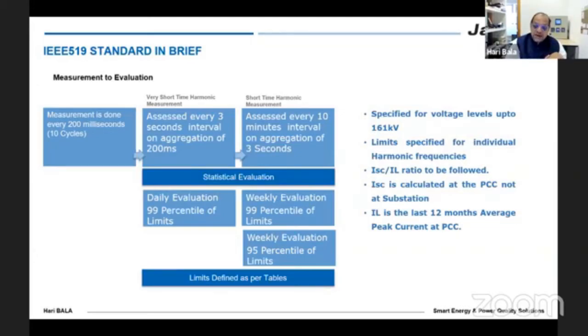Then they say the ISC by IL ratio depends on the location of the point of common coupling and the impedance over there. This means the values can be adjusted according to where the customer is in the network, whether very close to the substation or transformer, or far away from it. The limits can also vary, so there are multiple levels of consideration so that customers can accordingly generate their harmonics. So it becomes a calculation which has to be done before we start actually complying with IEEE 519. ISC is again calculated at the point of common coupling, and not at the distribution substation. So it is at the point of common coupling where the utility is giving power to the consumers.